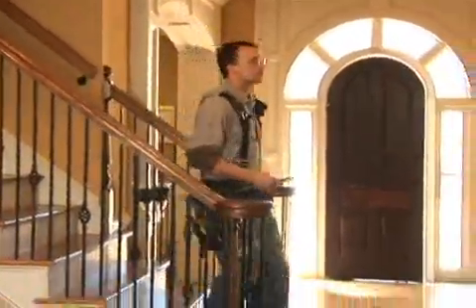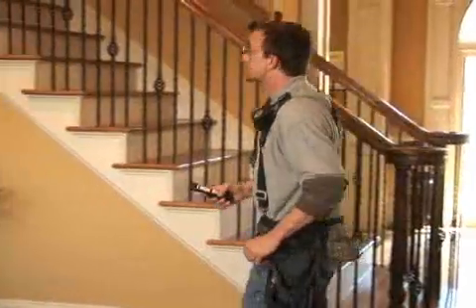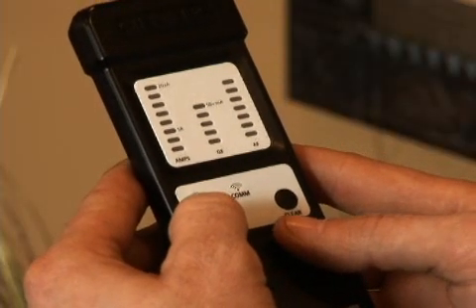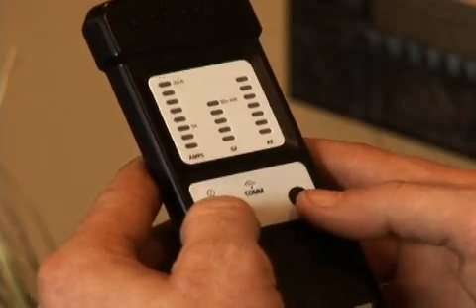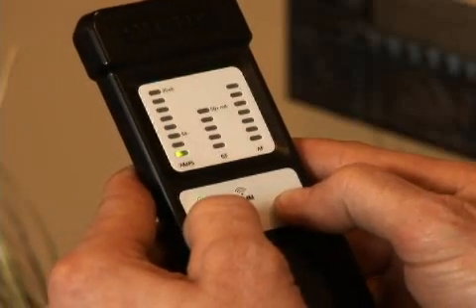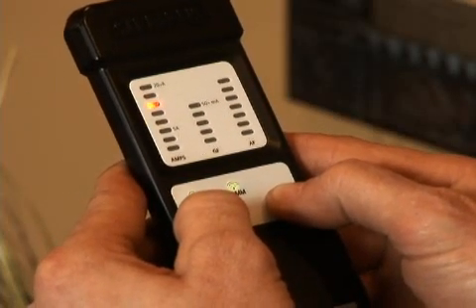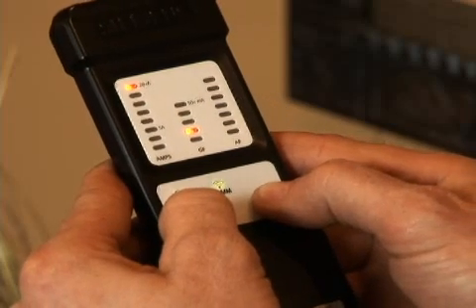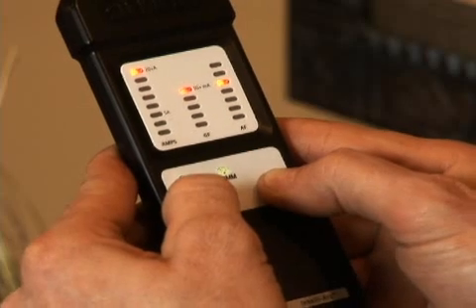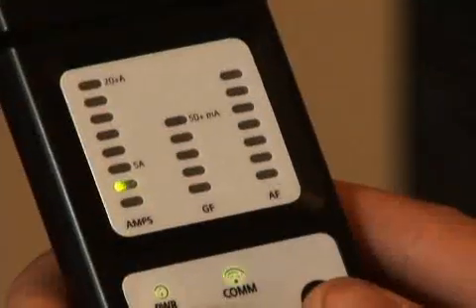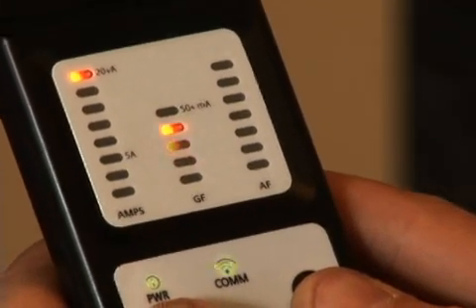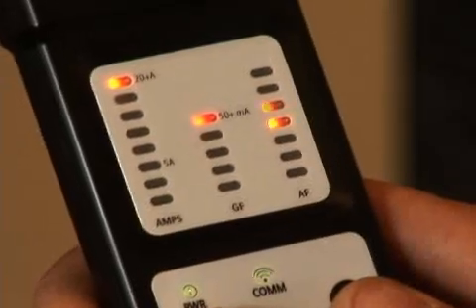Before taking you through the operating instructions, let's look at the LED test procedure which should be performed before operating the handheld device. Turn off the handheld device. Press and hold the clear button on the handheld device, then press the power button while continuing to hold the clear button. The LED columns will light up one by one and each top LED will remain on so long as the clear button is pressed. If any LED fails to illuminate during the procedure, then the handheld device must be replaced. Once the clear button is released, the top LEDs will clear and the handheld is ready for operation.